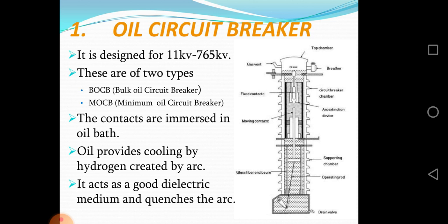There are two types: BOCB (bulk oil circuit breaker) and MOCB (minimum oil circuit breaker). The contacts are immersed in an oil bath. Oil provides cooling by hydrogen created by the arc; it acts as a good dielectric medium and quenches the arc.